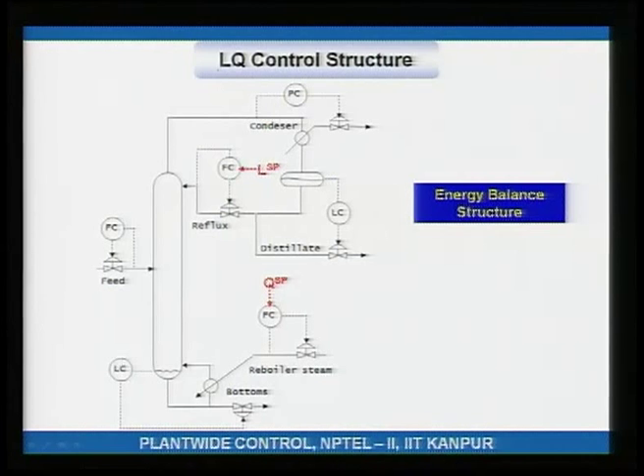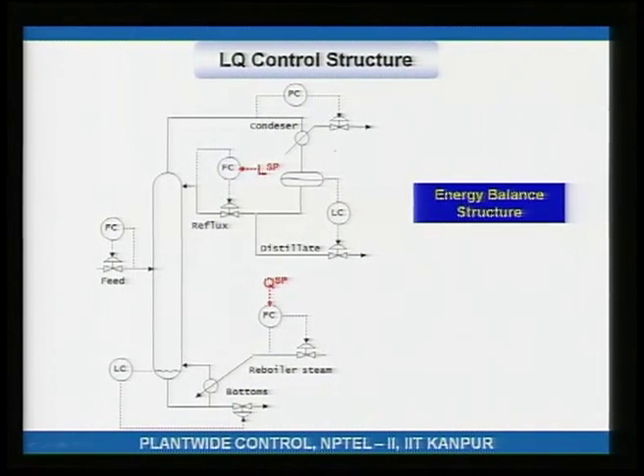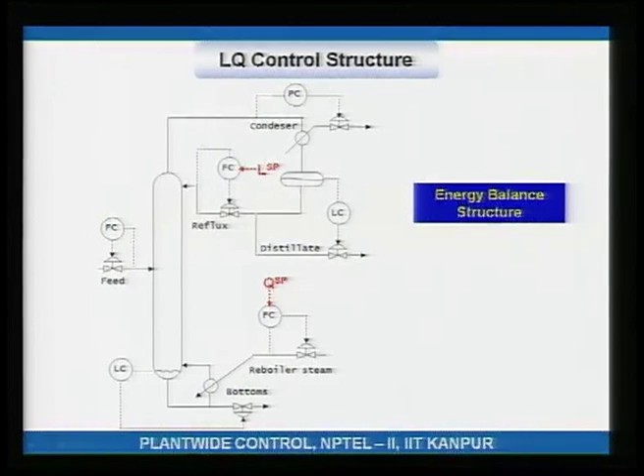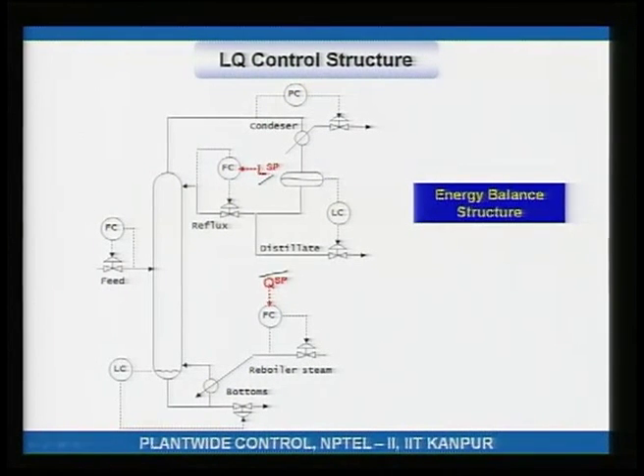The first is called the LQ control structure. In this structure, the reflux drum level is controlled by the distillate, the bottom sump level is controlled by the bottoms product stream, and the pressure is controlled by adjusting the coolant flow rate in the condenser. Once these level and pressure loops are fixed, the operator can adjust the reflux set point (L) and the steam flow set point (Q) to get the desired separation. Hence it is called the LQ structure.